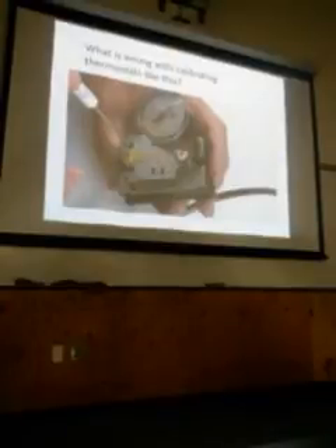Okay, and finally, what's wrong with calibrating a thermostat like that? Yeah, you're affecting the calibration point because your hand is affecting it. Did anybody notice like a 2 to 3 pound difference when you put your hand by the stat when you were calibrating last week? Yeah, I mean it's pretty substantial. And you got the radiant heat of your body also, because when you're doing this, it's best to stand back. Your breath as you're breathing on it.